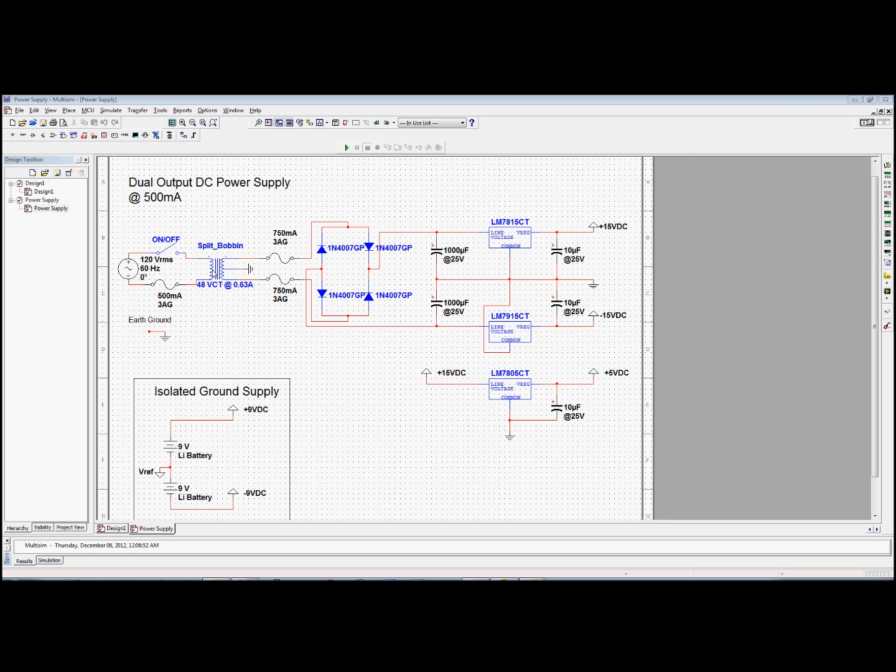Here I include actually three fuses. On the primary it's a 500 milliamp fuse. On the secondary it's two 750 milliamp fuses. This is a similar tab design by the way.